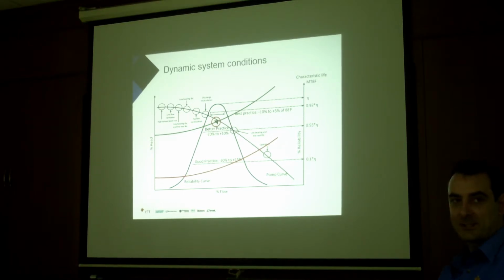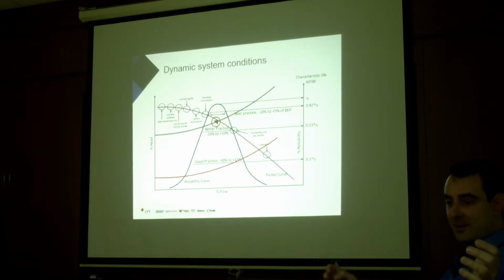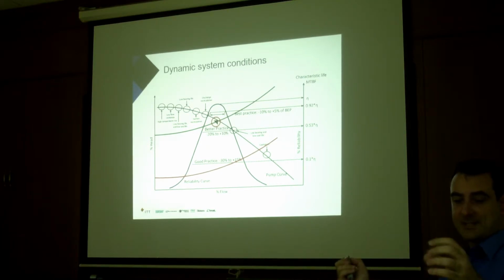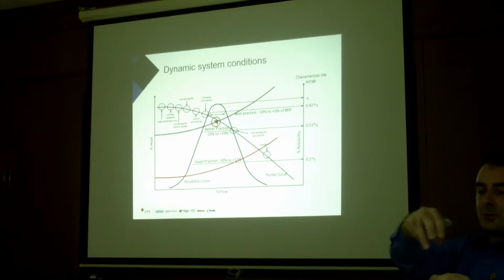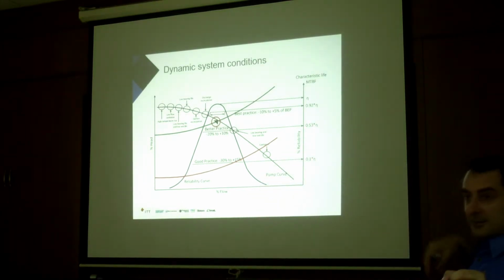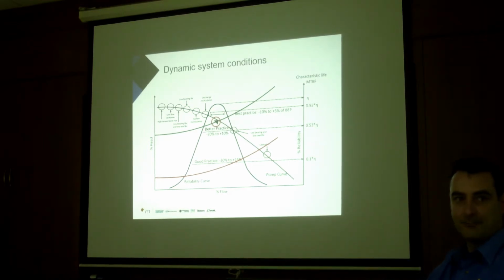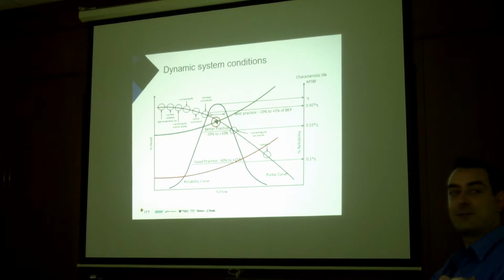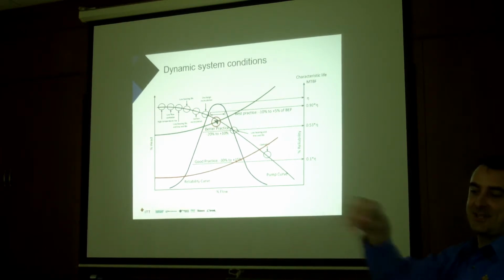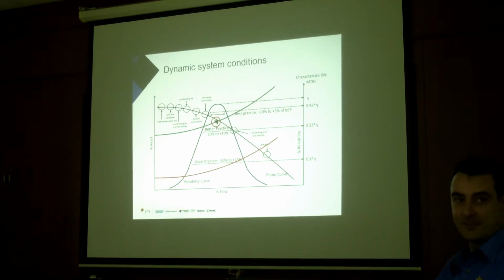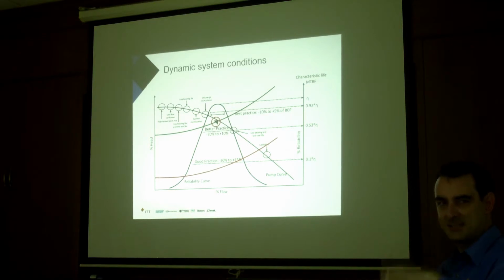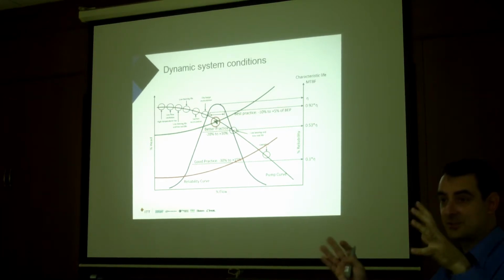That's our easiest application. The tank terminal ones that are harder are when, like you're saying, there are different pipe lengths. The Vopak Banyan's problem is that the pump is fixed and they can draw from a tank here, here, anywhere. Yes, the friction curve changes every single time. So that's where they design for the worst case, but actually the best case occurs all the time. So they always have cavitation and vibration noises. You see here it says cavitation. They're always off the end of the curve. So every application's a little different in how we can do it, but like the same customer, Vopak, but a different site. It's only a small pump.